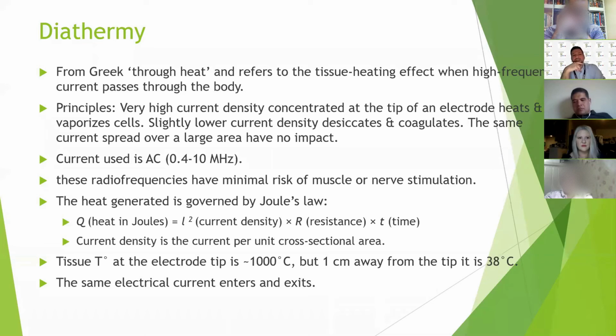The heat is generated through Joule's law, which is the amount of heat in joules is equal to the square of the current density multiplied by the body's resistance multiplied by time. So the more fluid there is in the body, the less the resistance, which means the less the heat. Hence, the diathermy doesn't work underwater. The tissue temperature that can develop at the tip of the diathermy is about 1000 degrees centigrade. But it reduces to 38 degrees only 1 centimeter away. And that is because it dissipates over a bigger surface.